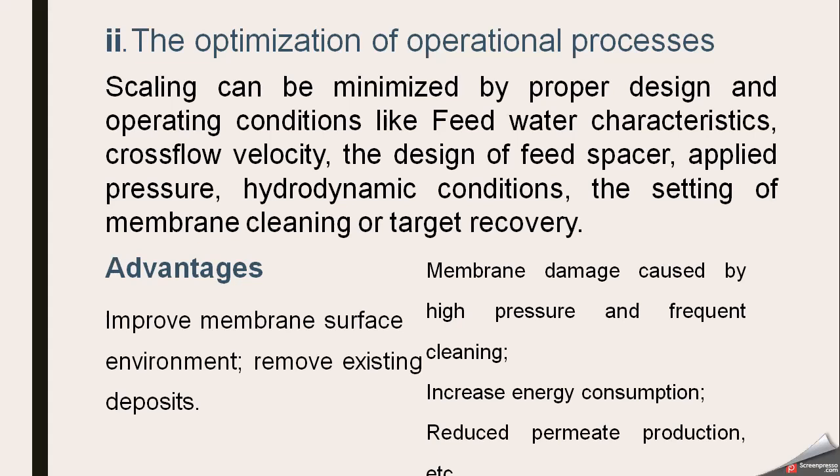So we have to compromise, or basically optimize, the applied pressure and other hydrodynamic conditions and the setting of the membrane cleaning or target recovery. For cleaning, we will determine the membrane cleaning frequency, and then target the recovery, that is, how much permeate we can get without compromising our process and without promoting scaling. The advantage is an improved membrane surface environment and removal of existing deposits.